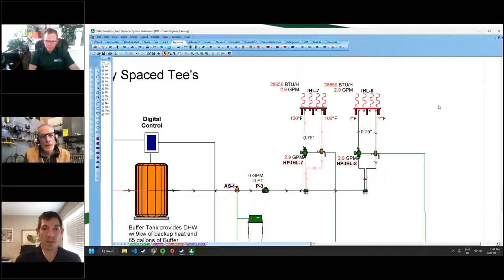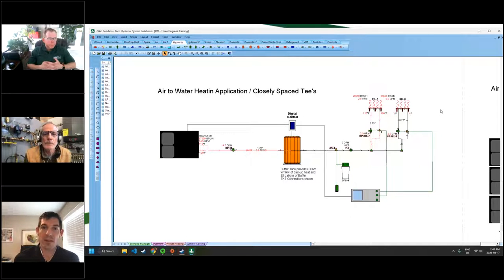Any thoughts, guys? One of the other things that's hard to plan for there is, how do you know, is zone one always on? Is it always taking 120 down to 100? Or does zone one come on only when the mother-in-law is in town? And then it's just so hard to even know what to expect your temperature would be. From a troubleshooting contractor standpoint, how do you figure that out? How do you figure out that this heat emitter isn't working on zone six if it's all in series like this? Or if there's just realistically no potential for that to ever get warmer than 80 degree supply temperature, and you can't really know if there are zones that are on and off at different times. You don't know what to plan for.